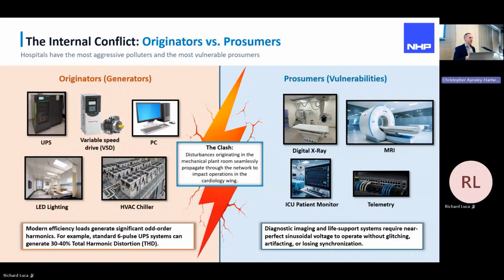So in our quest to save energy, we install VSD chillers, LED lighting. Hopefully they're not the cheap and nasty ones that blow every 6 months, but we install all these products to achieve the benefits of reduced energy, but at the cost of harmonic distortion. There's 30–40% in the system. And they're the originators, but the prosumers producing harmonics and also consuming harmonics.